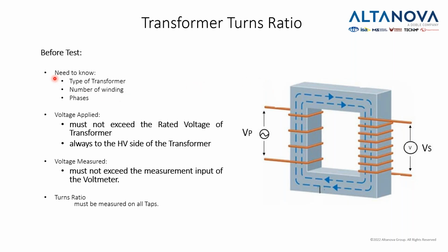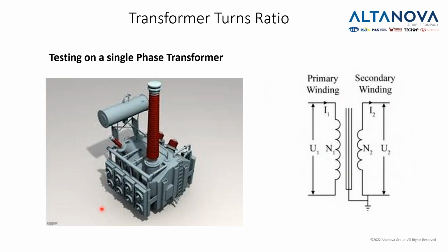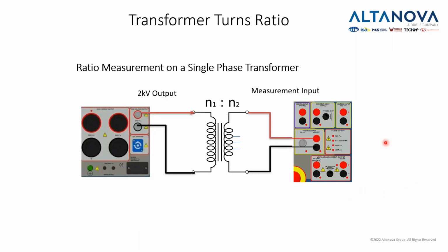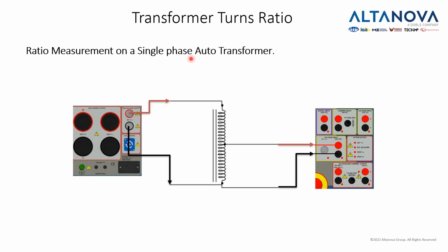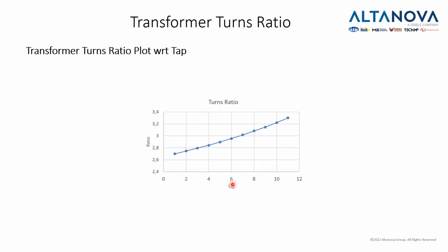So the important thing is that the applied voltage must not exceed the rated voltage of the transformer, always on the high voltage side, as we mentioned, and also we must not exceed the measurement input of the voltmeter. That also needs to be taken into consideration, and the test needs to be done on all taps. So if we have a single phase transformer, we will generate on the primary and measure on the secondary side, like we see here, for example. And if we have an auto transformer, we will do our test as shown in this slide.